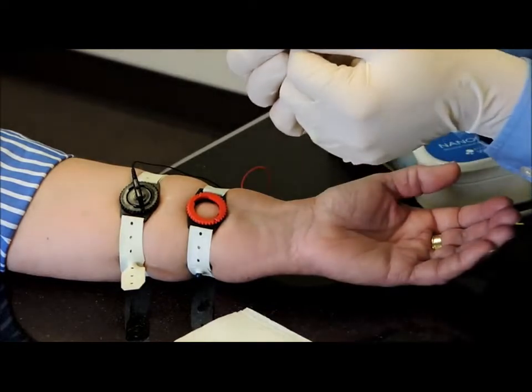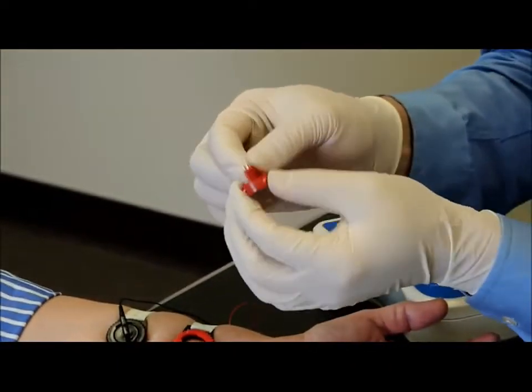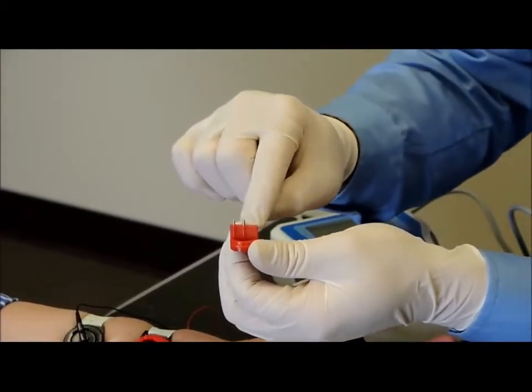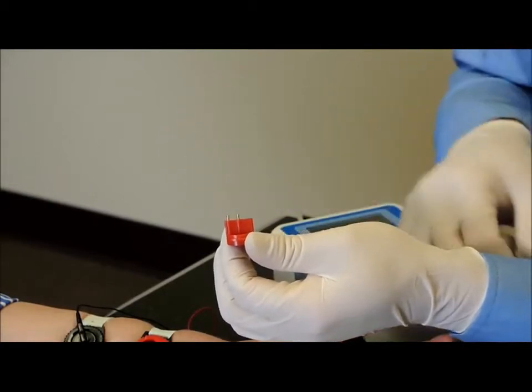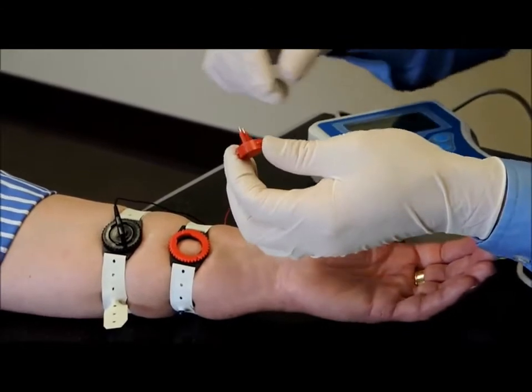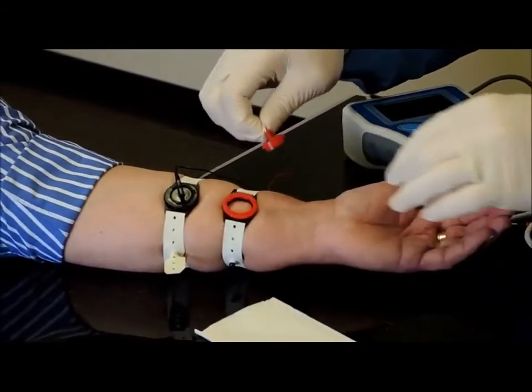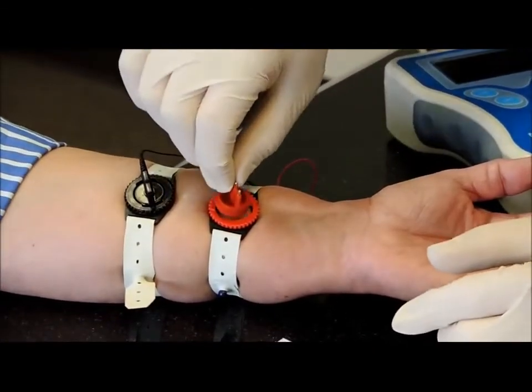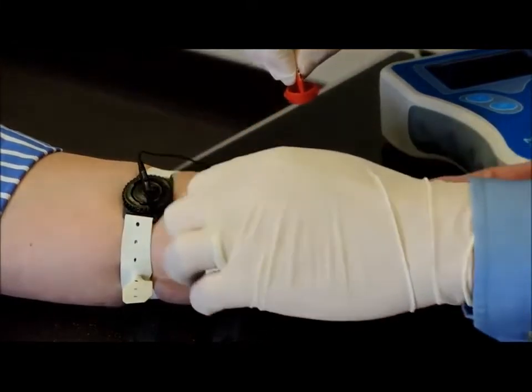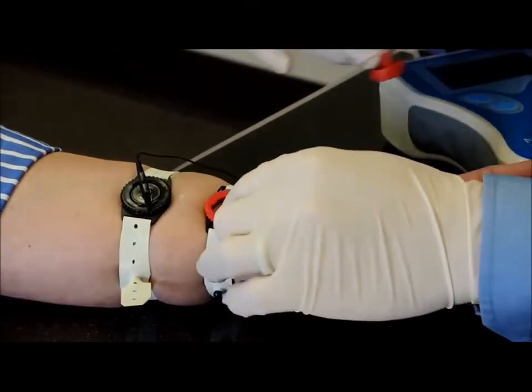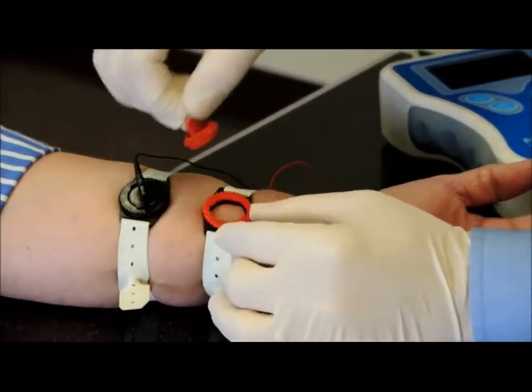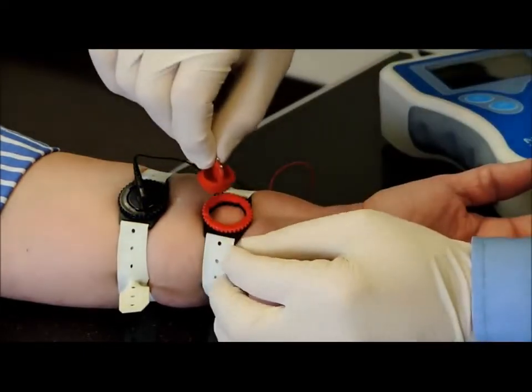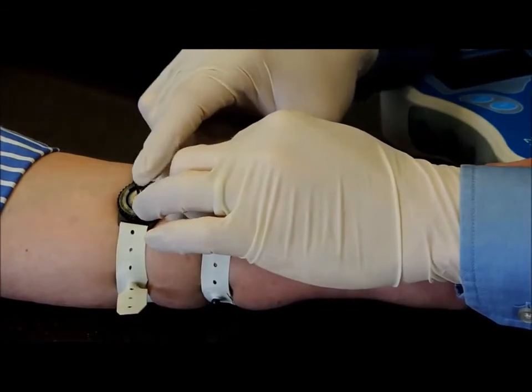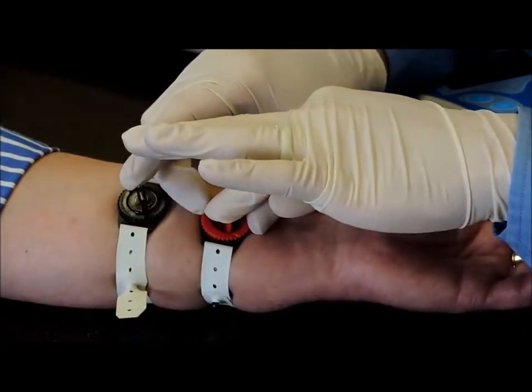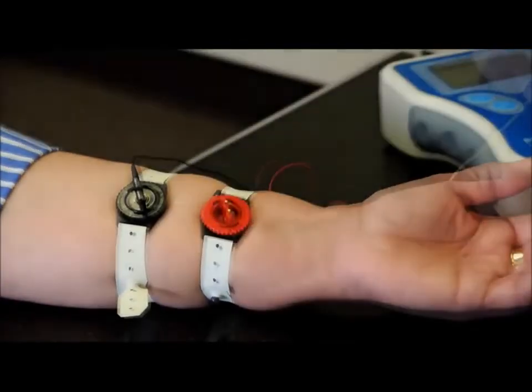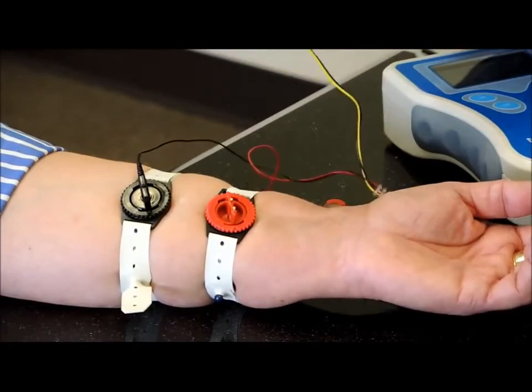The sensor cell has a small hole in the bottom that the sweat will funnel into, and then there's a path inside going from this electrode to this other electrode, and it measures the conductivity as it's being collected. I like to put the sensor cell in first before I connect it to the cable, just to make sure the sensor cell is seated properly. So again, I move the ring. I notice a small piece of dust from the swab. I'll take that out. I move the ring so that these flanges on the sensor cell can go down all the way to the skin properly. I push down, and then I move the ring again 45 degrees, and so it locks in place. So now with the sensor cell in place, I'll connect the cable to the sensor cell.